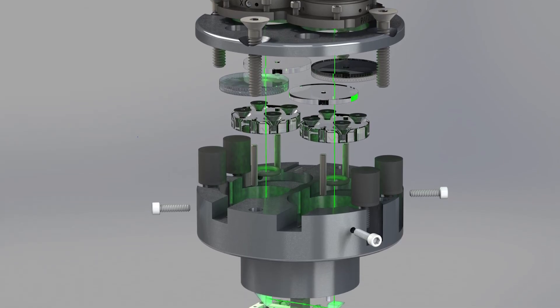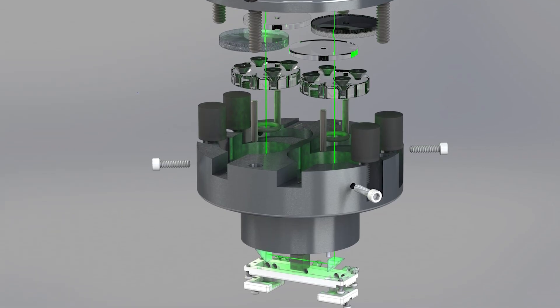The entry is the Electro-Optical Sensor, or EOS. EOS is set to revolutionize the field of high voltage measurement. It is an innovative device that can measure up to 20 million volts with no physical contact.